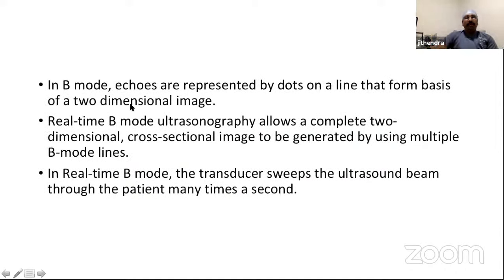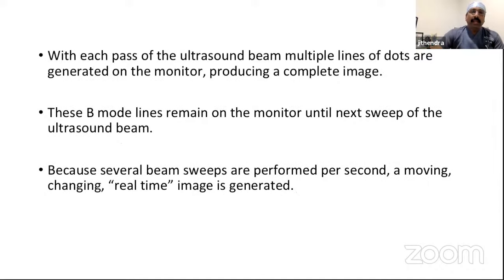So in B mode, echoes are represented by dots on a line that forms the base of the two-dimensional image. When you do real-time B mode ultrasonography, it allows a complete two-dimensional cross-sectional image to be generated by multiple B mode lines. In real-time B mode, the transducer sweeps ultrasound through the patient many times a second. With each pass of the ultrasound beam, multiple lines of dots are generated on the monitor, producing a complete image. These B mode lines remain on the monitor until the next sweep of the ultrasound beam. Because several sweeps are produced per second, moving or changing real-time images are generated. This is the basic method of how a real-time image is created by an ultrasound machine.